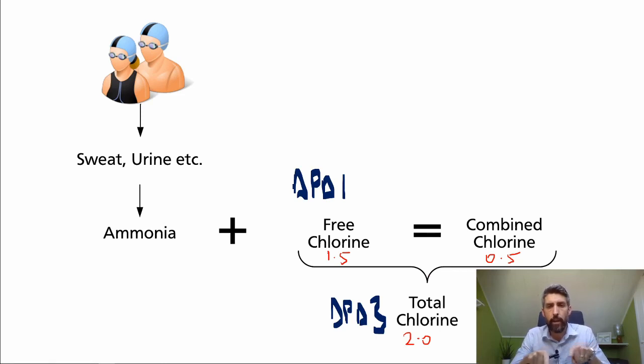So free chlorine is the first test with the DPD-1. Follow that up with a test on total chlorine with a DPD-3. And you'll find that the total chlorine should never be less than the free chlorine because that wouldn't make any sense. The total chlorine is either going to be the same as the free chlorine, in which case you haven't got any combined chlorine, or usually the total chlorine will be slightly more than the free chlorine. And it's the difference between the two that tells you how much combined chlorine you've got.